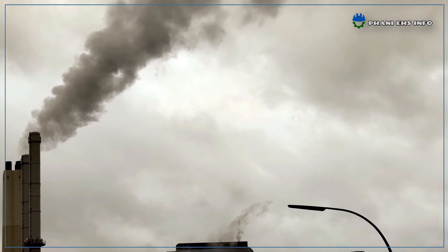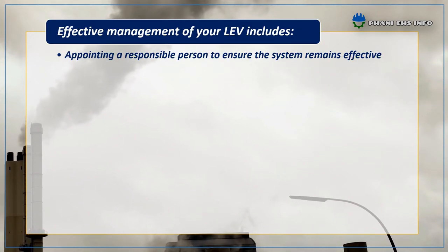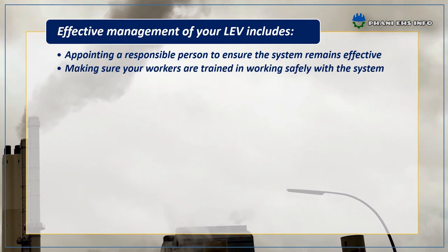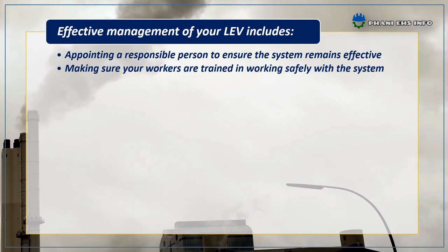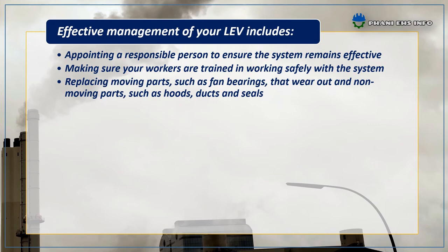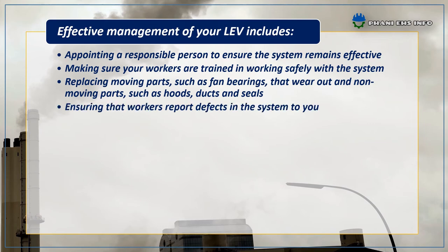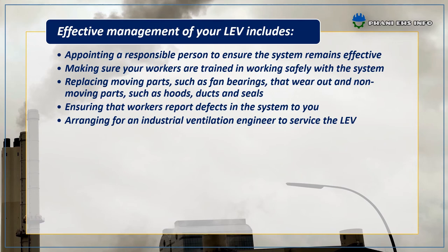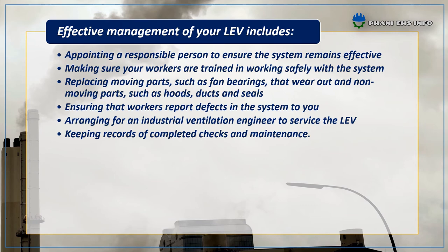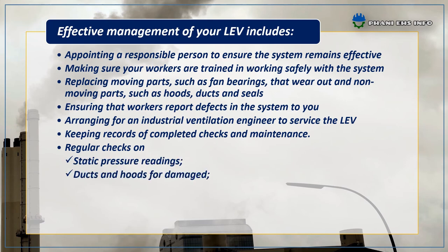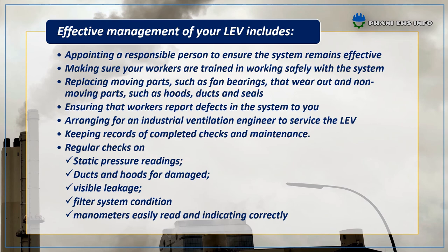Finally, effective management of LEV systems. First, appoint a responsible person to ensure the system remains effective. Second, make sure your workers are trained in working safely with the system. Third, replace moving parts such as fans and bearings, as well as non-moving parts such as hoods, ducts, and seals that wear out. Fourth, ensure that workers report defects in the system. Fifth, arrange for an industrial ventilation engineer to service the LEV system. Sixth, keep records of completed checks and maintenance. And conduct regular checks on static pressure readings, ducts and hoods for damage, visible leakages, filter system conditions, and manometers to confirm they are readable and indicating correctly. This covers the basics of industrial ventilation.